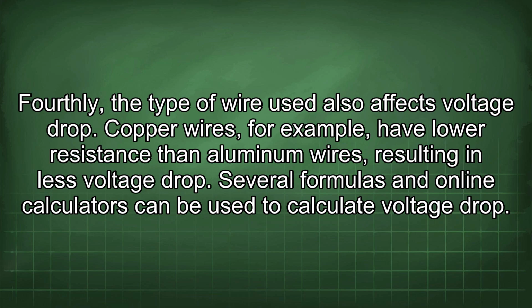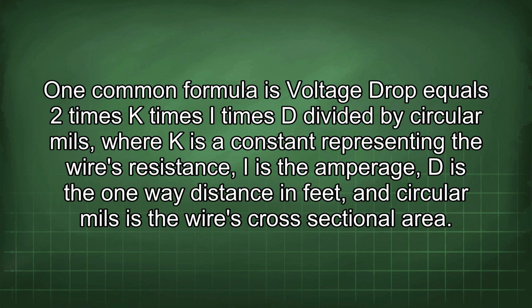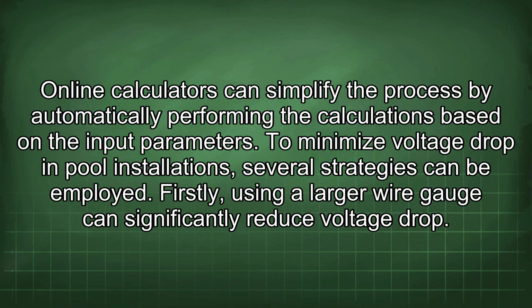Several formulas and online calculators can be used to calculate voltage drop. One common formula is voltage drop equals 2 times K times I times D divided by circular mils, where K is a constant representing the wire's resistance, I is the amperage, D is the one-way distance in feet, and circular mils is the wire's cross-sectional area. Online calculators can simplify the process by automatically performing the calculations based on the input parameters.